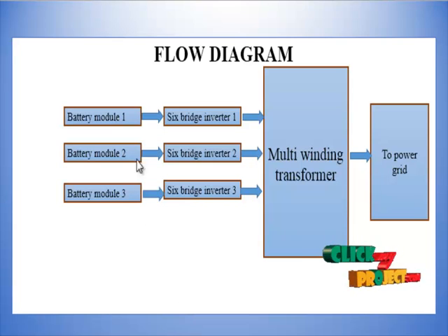This is the flow diagram of our product. This diagram consists of 3 battery modules, and the battery modules are connected in parallel. The output of the battery source is fed into the 6-bridge inverter. Each inverter has 6 thyristors, IGBTs or MOSFETs. Here we are using IGBTs, and each inverter is connected in parallel with its DC source. Then the output of the inverter is fed into the multi-winding transformer. The multi-winding transformer is nothing but 3-phase transformers separately connected, and the output of the multi-winding transformer is fed to the power grid.